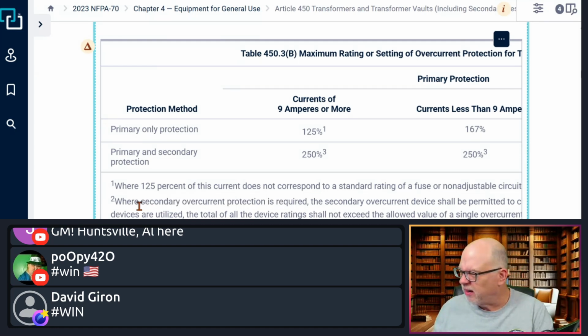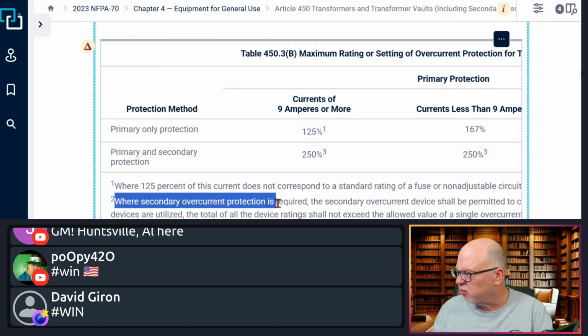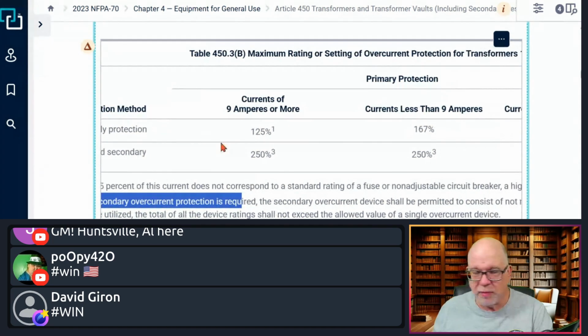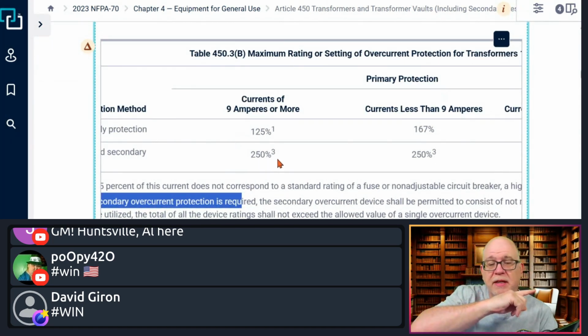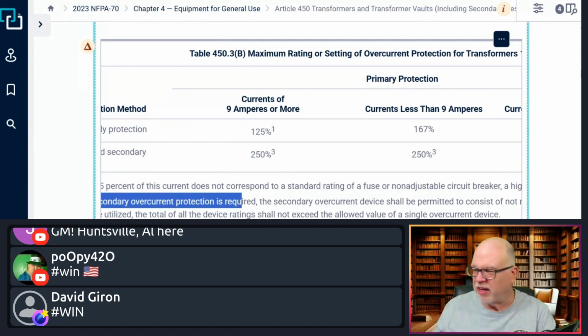Okay, so now where does it say here? It says where the secondary overcurrent protection is required. Let's assume it is because you're using the 250% option for the primary, up to 250, and then you're doing the secondary protection.